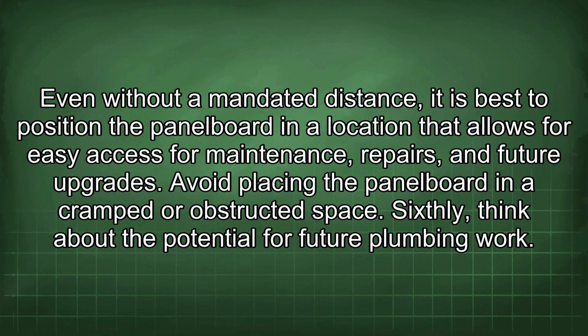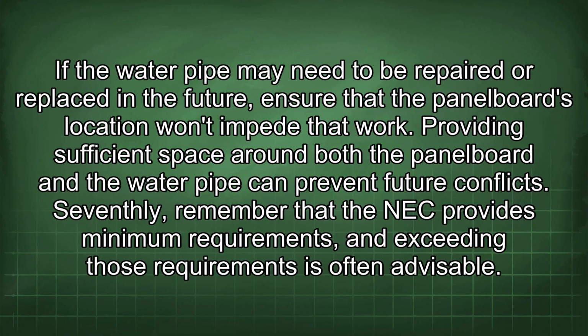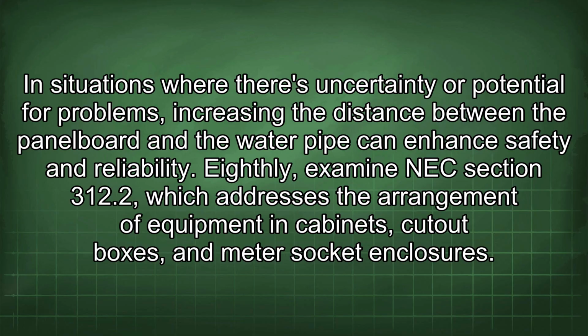Sixthly, think about the potential for future plumbing work. If the water pipe may need to be repaired or replaced in the future, ensure that the panelboard's location won't impede that work. Providing sufficient space around both the panelboard and the water pipe can prevent future conflicts. Seventhly, remember that the NEC provides minimum requirements, and exceeding those requirements is often advisable. In situations where there's uncertainty or potential for problems, increasing the distance between the panel board and the water pipe can enhance safety and reliability.